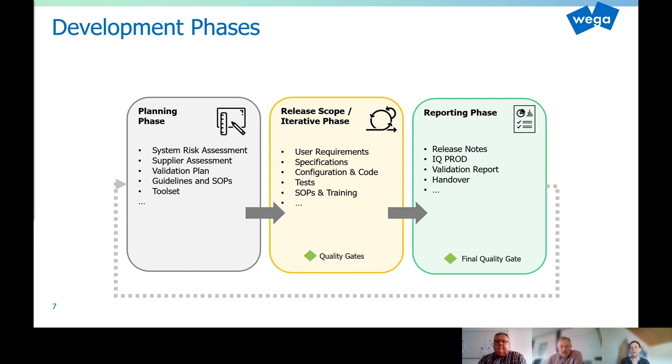Activities required for the deployment on the productive environment, like the IQ, will also be reported in the validation report. And we will also ensure that the procedures defined are trained, in order to keep the system in a validated state afterwards.